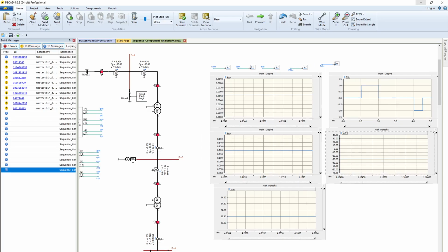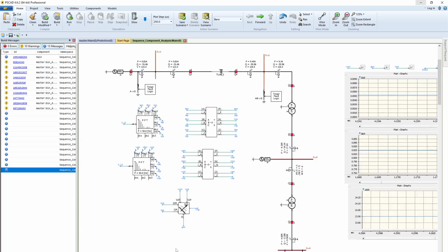In this way we can set our values, but you have to be careful when setting them, as I showed you just one case, like line to ground or double line to ground. Maybe you have to tune a little bit for all types of fault, because some faults are more sensitive. In that case you have to set it more carefully, but the calculation procedure is the same for all.